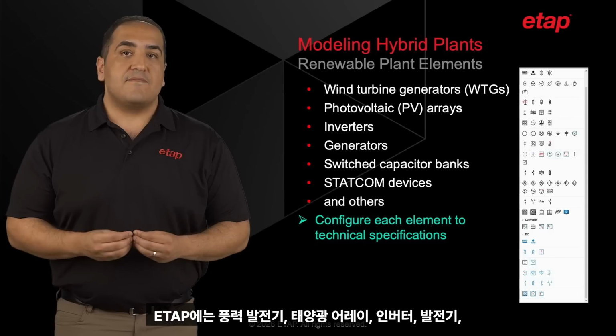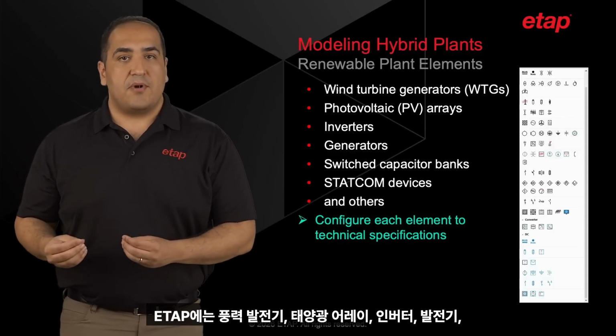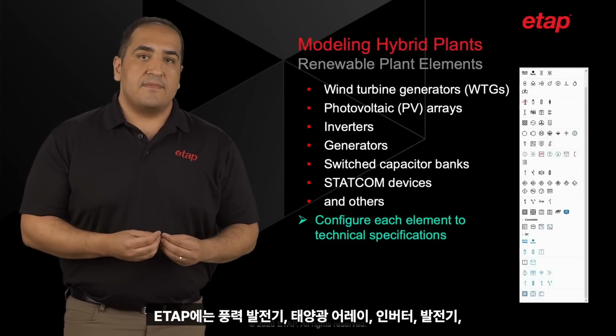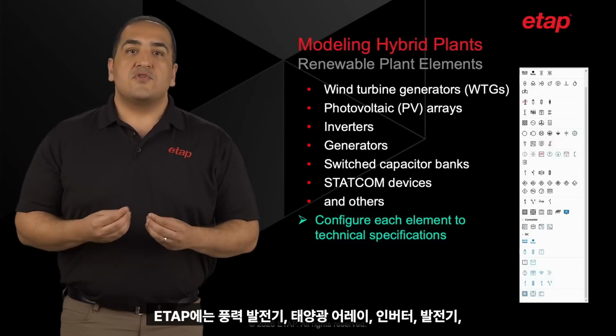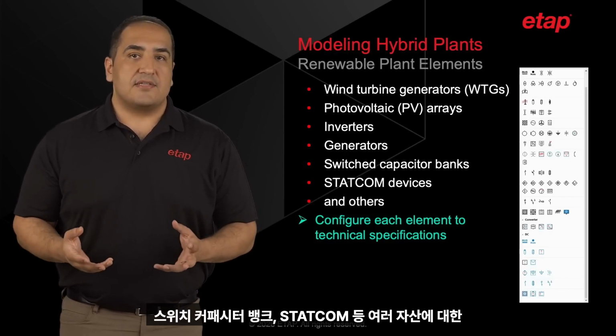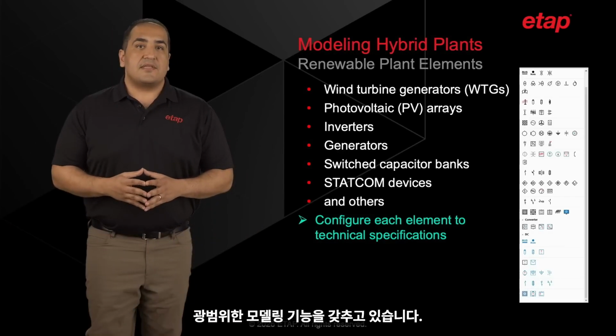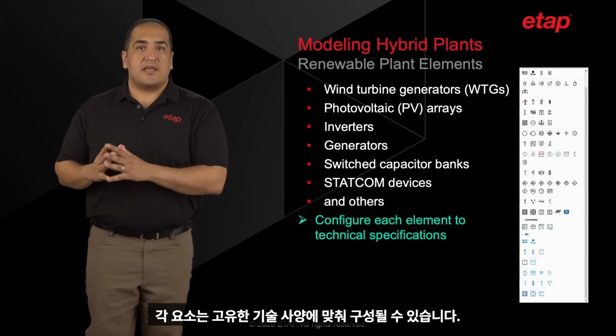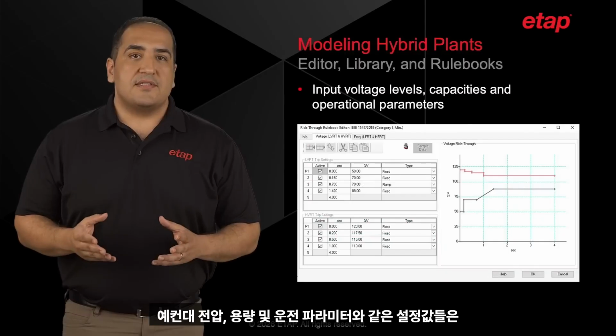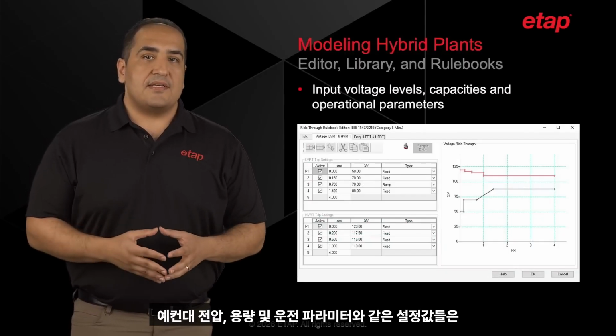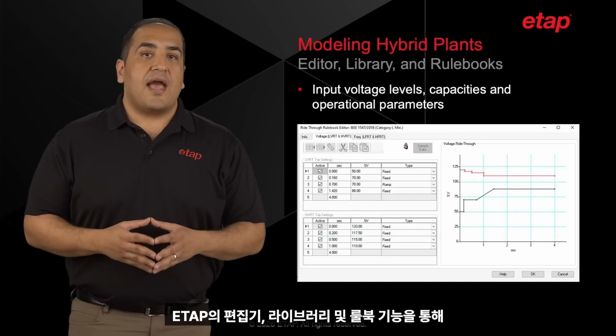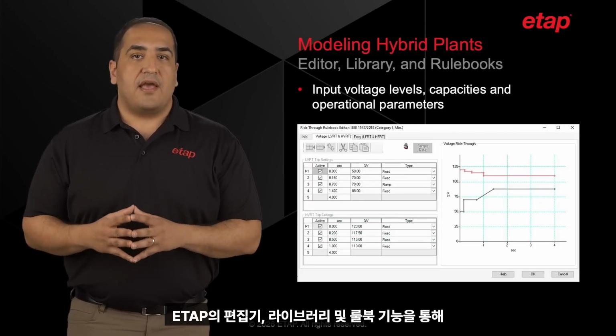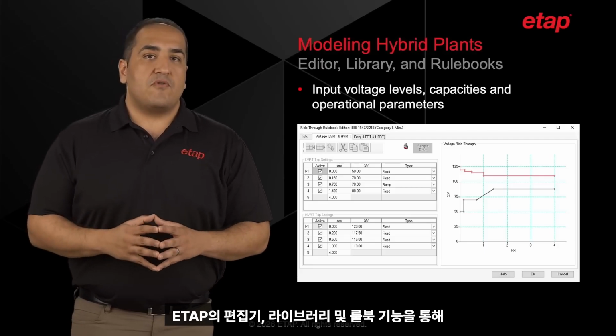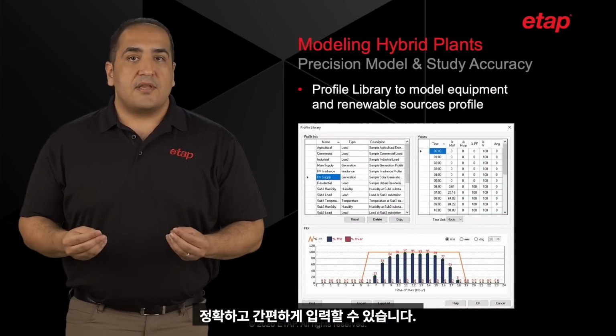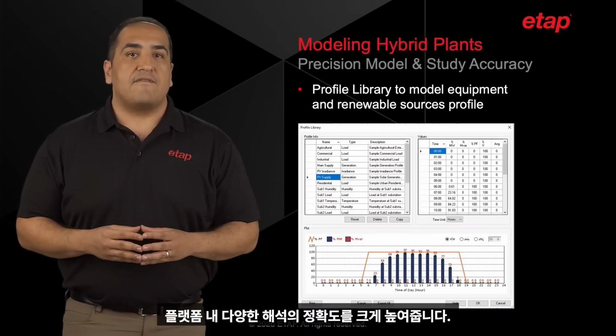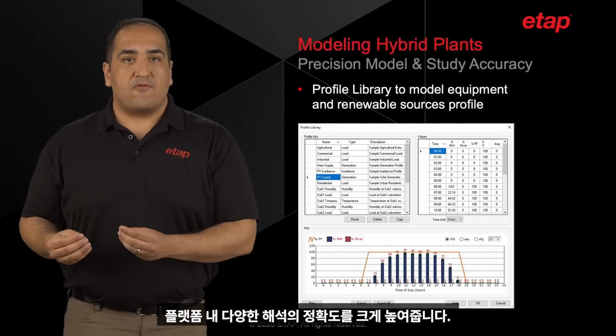ETAP includes extensive modeling capabilities for components such as wind turbine generators, photovoltaic arrays, inverters, generators, switched capacitor banks, and the STATCOM devices, and so on. Each of these elements can be configured according to their specific technical specification. For instance, settings like voltage levels, capacities, and operational parameters can be accurately inputted through ETAP's intuitive editor, library, and rulebook features. This allows for precise modeling that can greatly enhance the accuracy of various studies conducted within the platform.